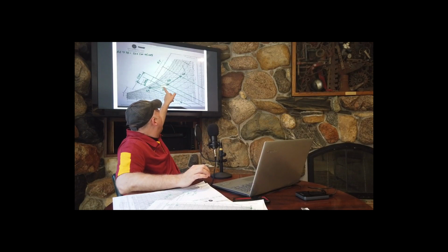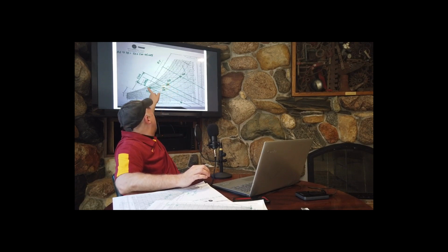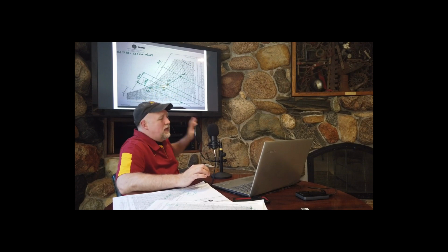Once we exhaust some of that room air and make it up with outside air, that air gets more moist and warmer, and then we cool it back down to supply air. That difference is the total coil load. Coil load is different from space load because we add ventilation air to it. And this is the type of calculation I would want to see on your homework and definitely on your final project.